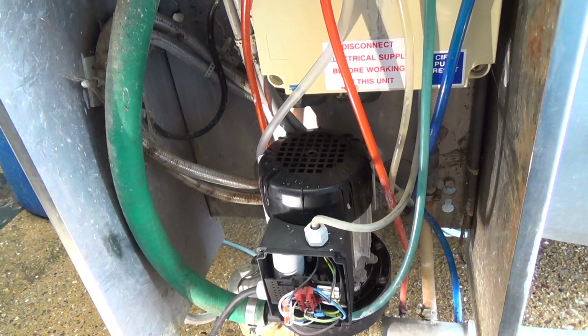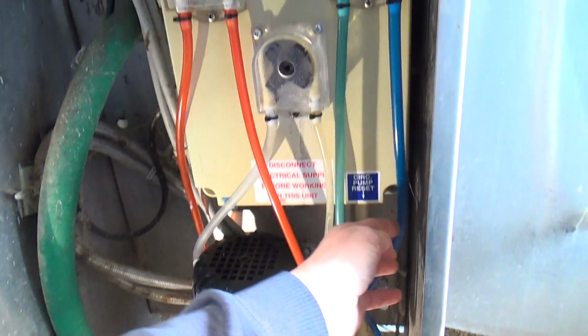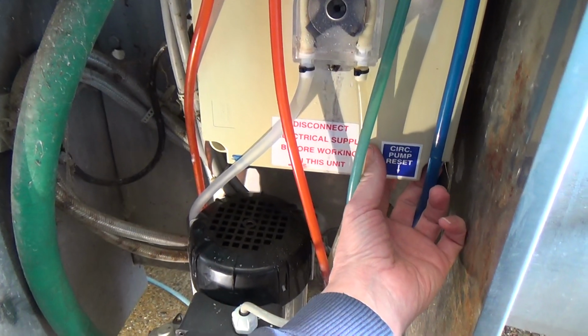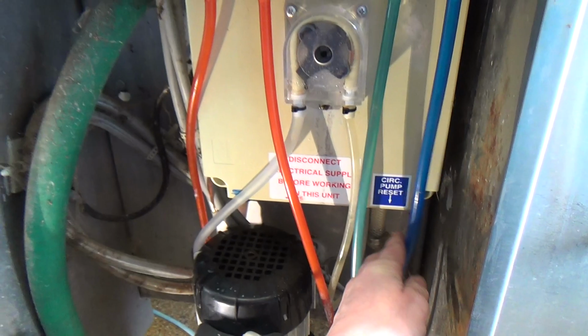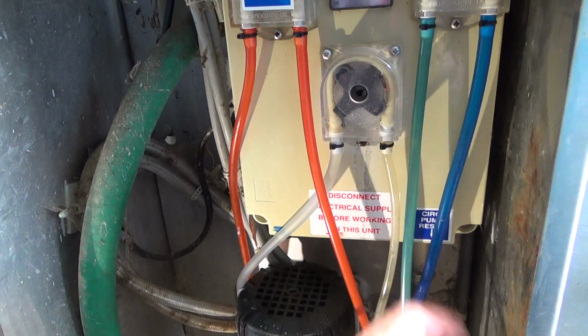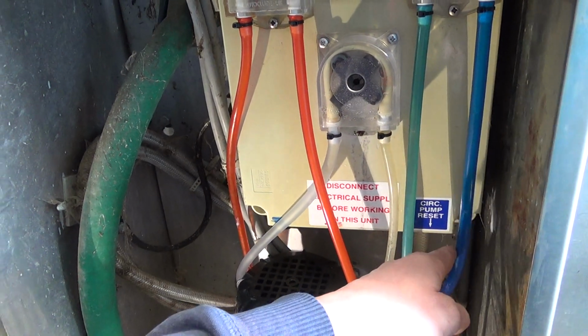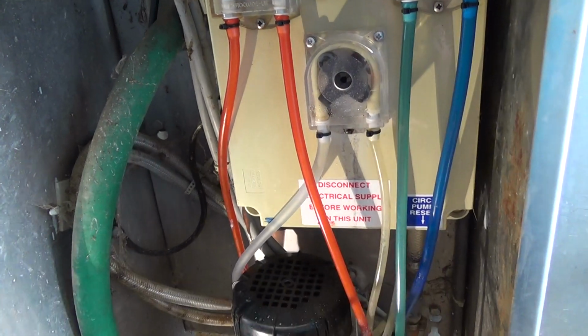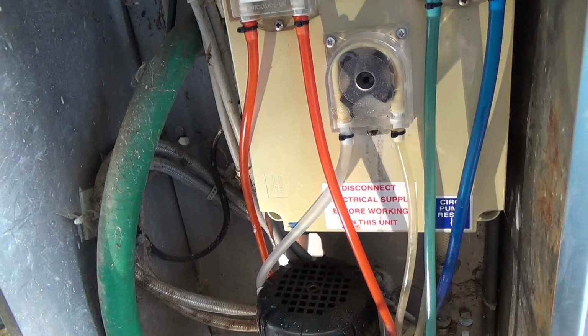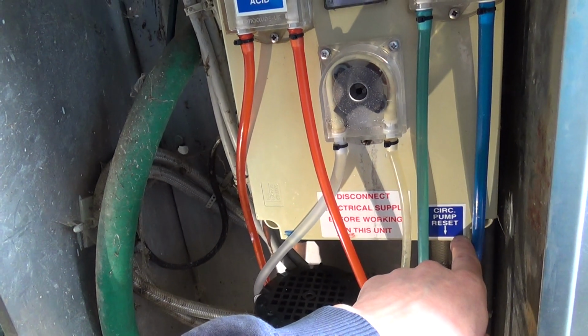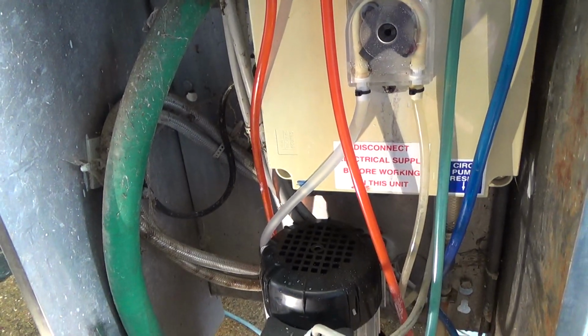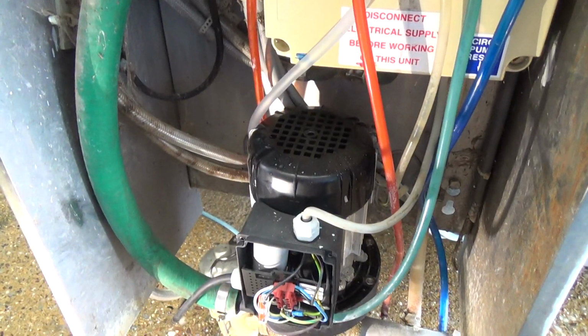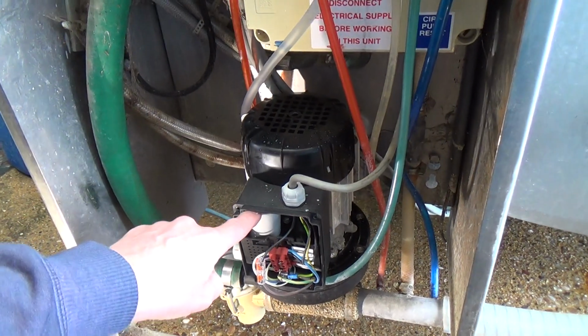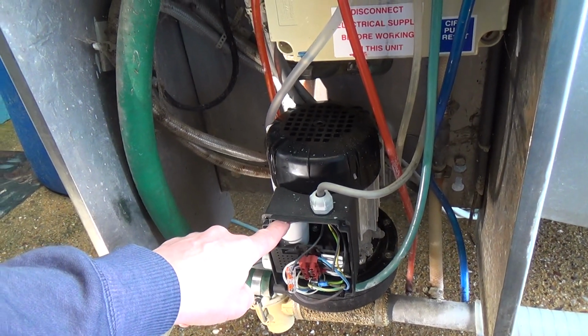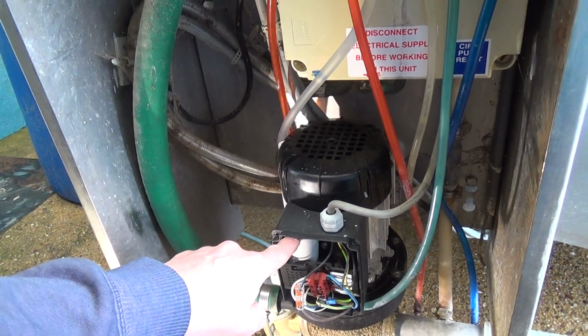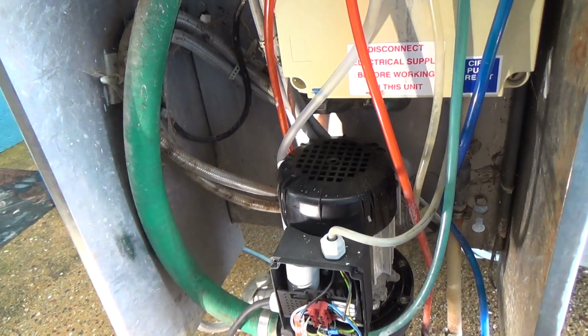And these little trips, they've only got so many trips in them. If they trip too many times, it wears them out. You know, they've got something like, I don't know, 30 trips or 50 trips in them in their lifetime. That's probably going to be a 20 plus year old thing anyway, so it's probably got a bit tired. Anyway, we're going to check the capacitor, make sure that's good, and then we'll test the run current.